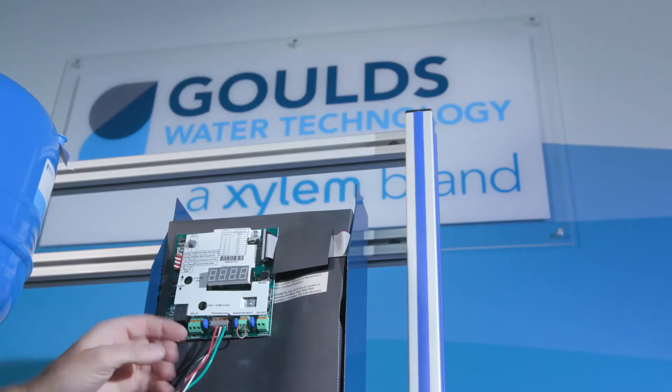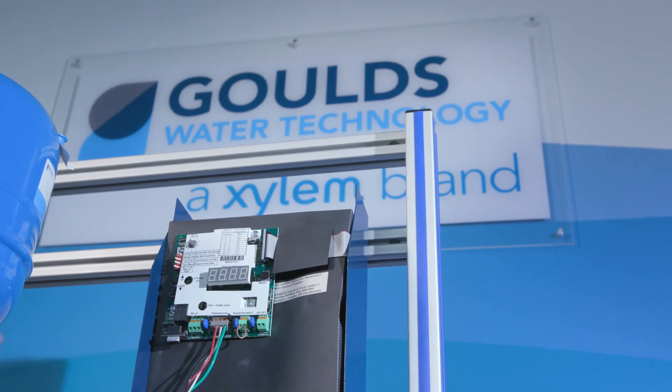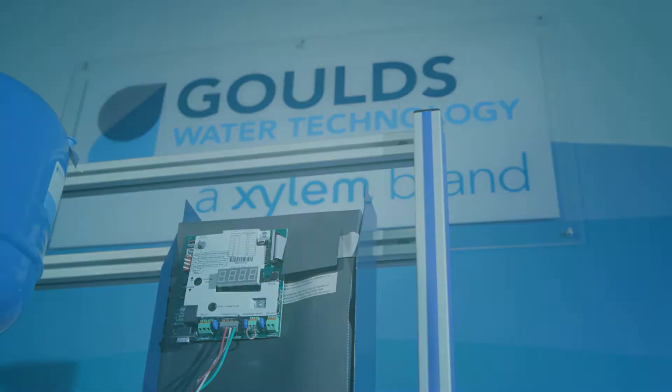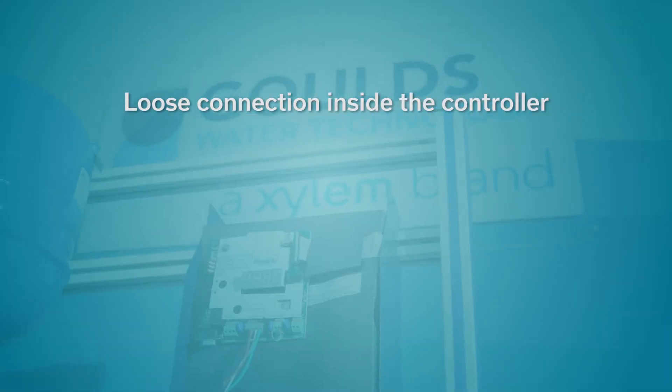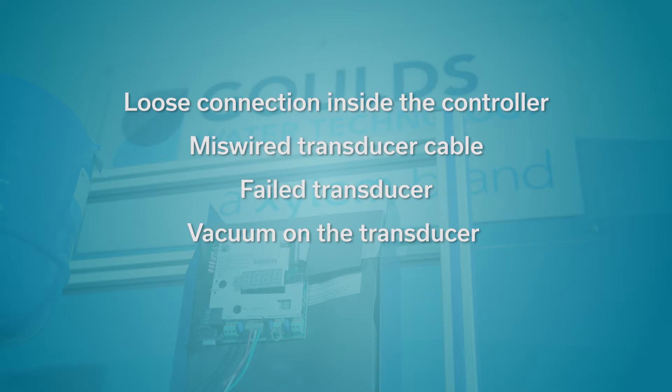We'll begin with the pressure transducer used on residential VFDs such as the Solo 2. Much of this information is in the installation manual IM260. We will check the following possible issues: loose connection inside the controller, miswired transducer cable, failed transducer, vacuum on the transducer, or a bad user interface board.